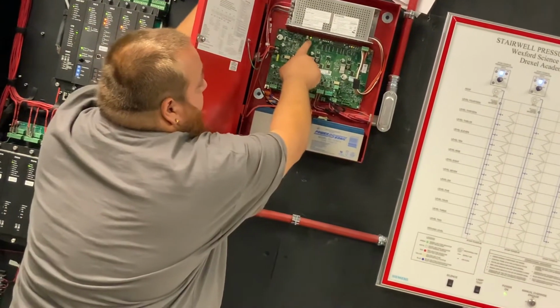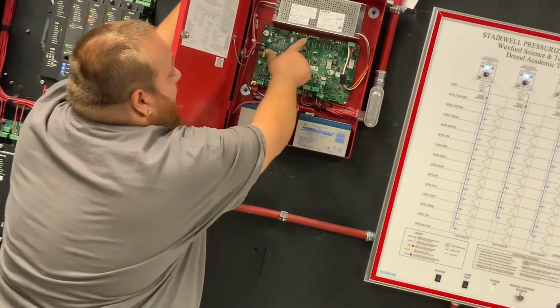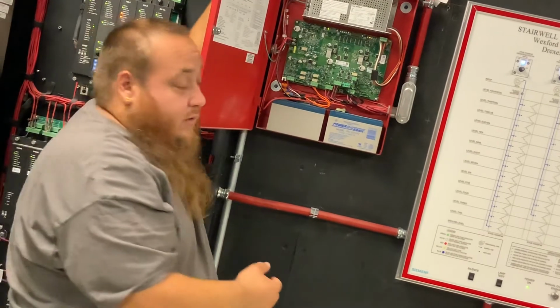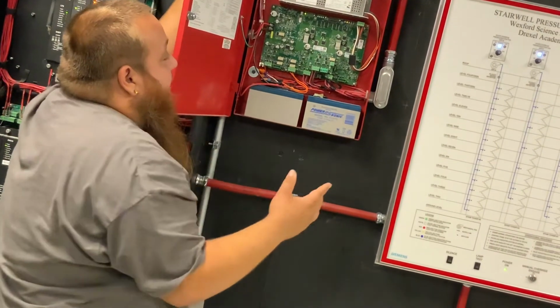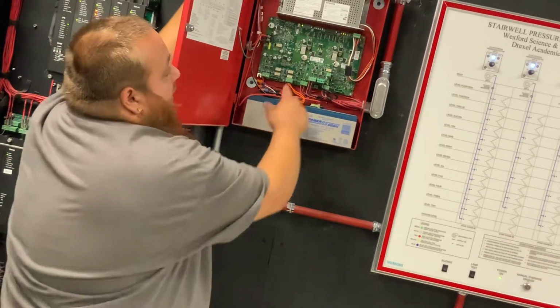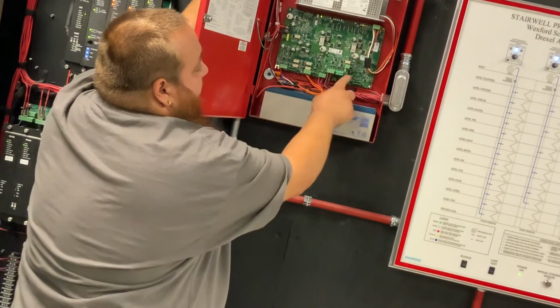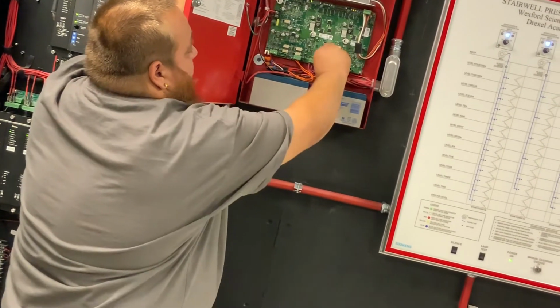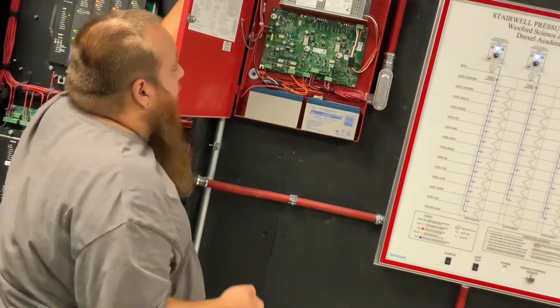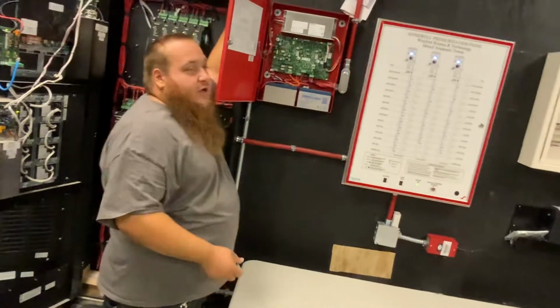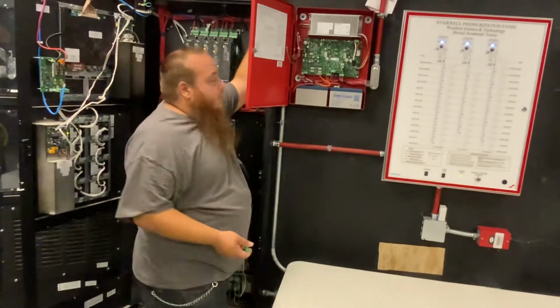Your green light here, that'll be your power light. Your second light right here, it'll say GND for ground reference. Anytime there's that issue, it'll glow. Right here, you have your 4 that are clustered together. That's your 4 outputs right here. Anytime, like say, one broke, got wet, got smashed from moving equipment, it could be anything.